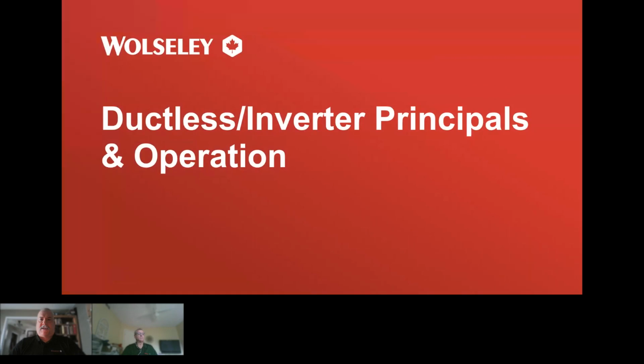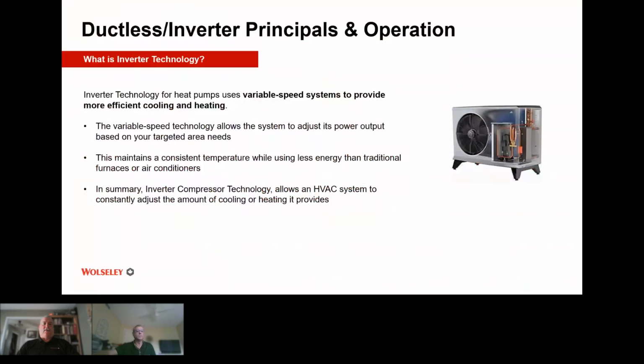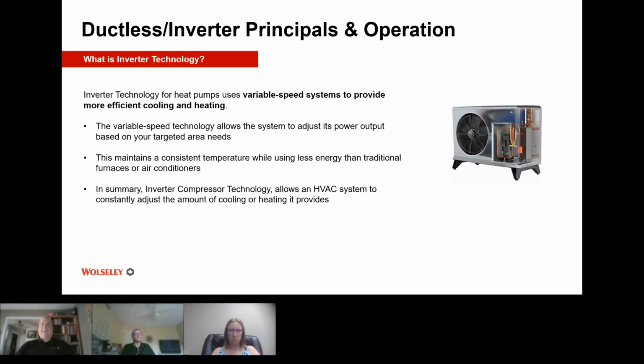All right, we're going to continue on with what Joey was talking about. We're going to expand upon ductless inverter principles and operations. What is inverter technology? Basically, inverter technology for heat pumps uses variable speed systems to provide more efficient cooling and heating. What this entails is that it's going to constantly adjust its power output based upon your targeted needs. This maintains a constant temperature while using less energy than traditional furnaces and air conditioners. In summary, inverter compressor technology allows HVAC systems to constantly adjust the amount of cooling or heating it provides.